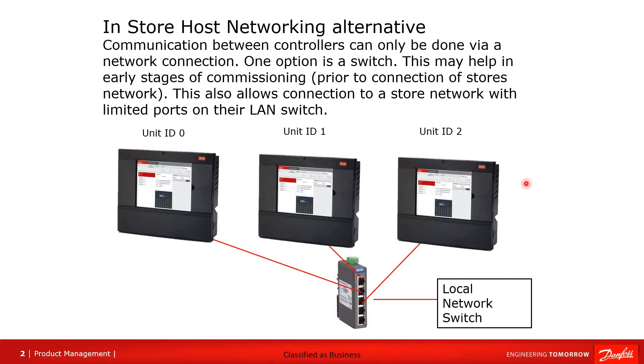Another form of creating a host network would not use the store's LAN, but we could put in our own. In this application, there's just a very small network switch being used. We take the three controls, wire each of them into this network switch, and now they will talk with each other, creating a host network with the three tied in. With the open ports, we could also tie a computer in and have access to these three controls. They do need to be programmed up — we'll talk about that in a bit.